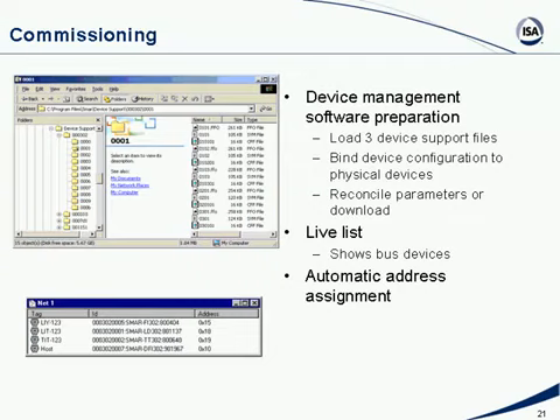So really, when you want to commission a device, you need to bind that device ID to the tag. And the way this is done, if it's not done automatically, all the new devices typically get shipped with a paper slip attached to it. Okay, this is called a commissioning tag, but people call them a dog tag. This dog tag has the device ID on it. So when the guy installs the device, he writes the tag on this dog tag and carries it back with him into the control room. So on this tag now, he has both the device ID and the tag.